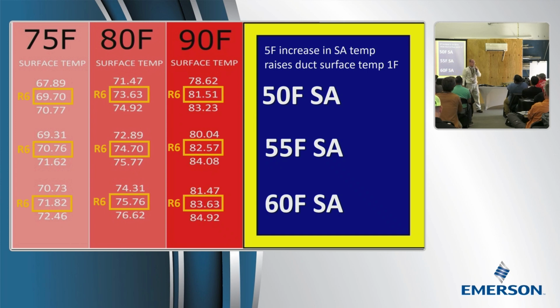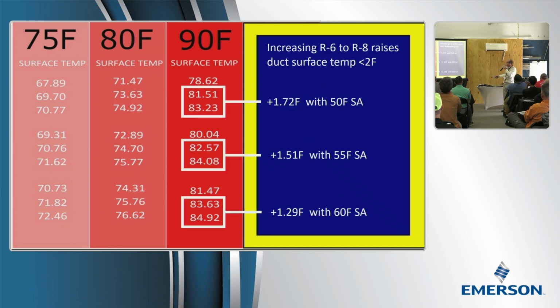So that's why we expect most of the condensation that we experience with these things to occur at 80 to 75 degrees. And when does that happen during rainy season in Florida? Every night. It's 95 in the daytime. Is it 95 at night? No, it's 75 to 80. And that's when your ducts are getting wet, while you sleep. While you're there on the service call, they're actually drying. So you can actually go to the customer and say, I checked it out, they're drying right now. See if it works for you. It didn't work for me, but try it.